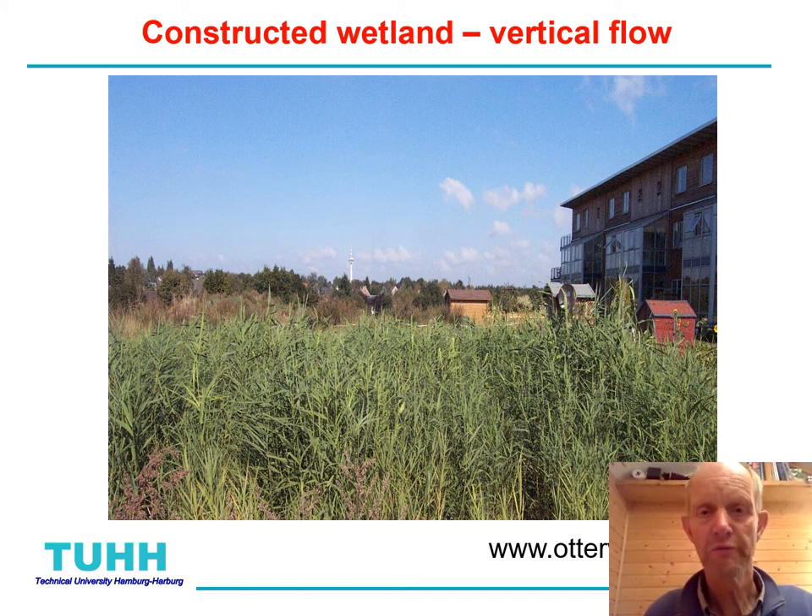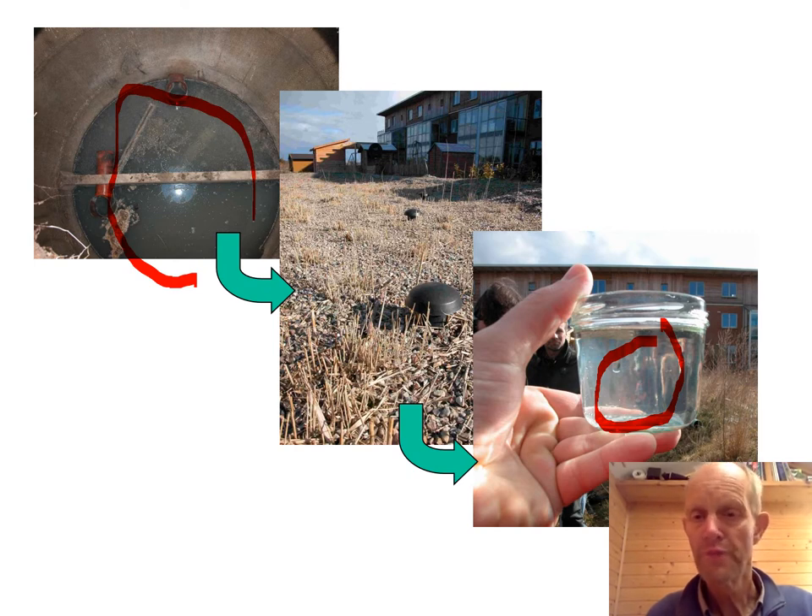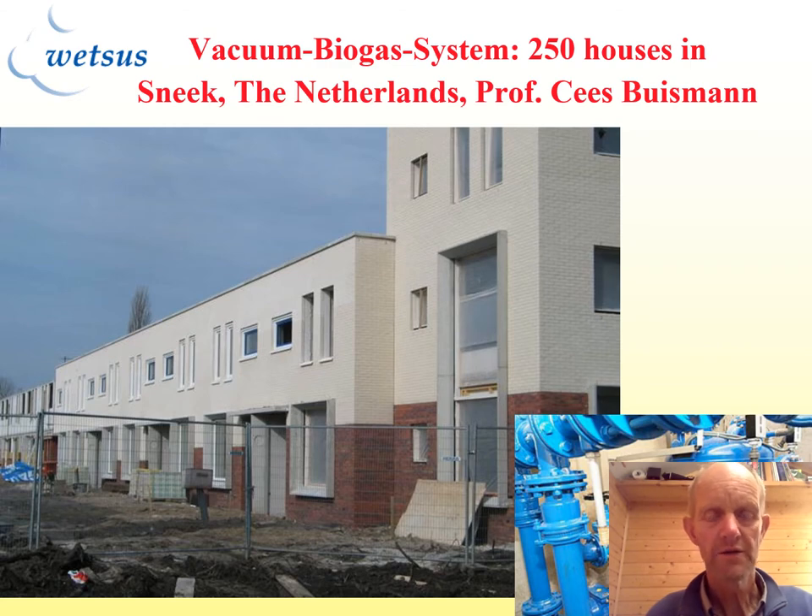After 20 years of operation, the system still works very well and the water looks very clean after treatment. Even though gray water is really dirty at the beginning, when we made further analysis we realized there are still residues of household chemicals that we wouldn't want to put into a river. Further treatment would be good, and use of more eco-friendly household chemicals would be advisable.